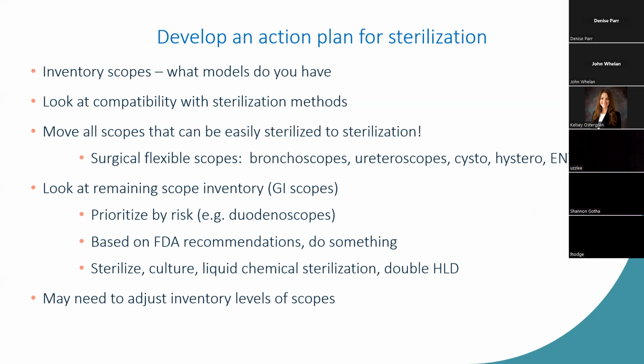So a way to approach this, find out, first of all, who's got what scopes. Look at compatibility with sterilization methods that already exist within your institution. Any that can be easily sterilized, move them to sterilization. Look at your remaining scope inventory, and I give the example here of GI scopes. Prioritize by risk, so elevate your elevator channel endoscopes to high risk. Based on the FDA recommendations, for those high-risk scopes, do something else or something more. And you may need to adjust your inventory level of scopes.